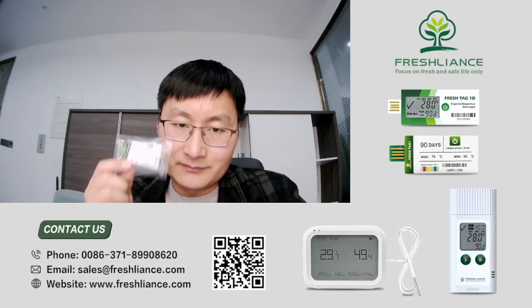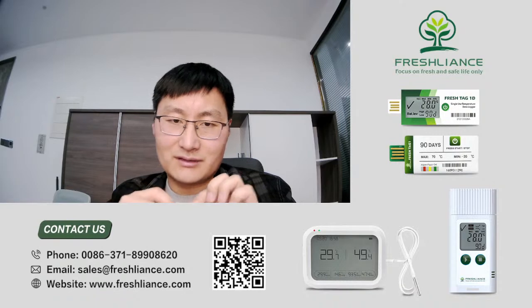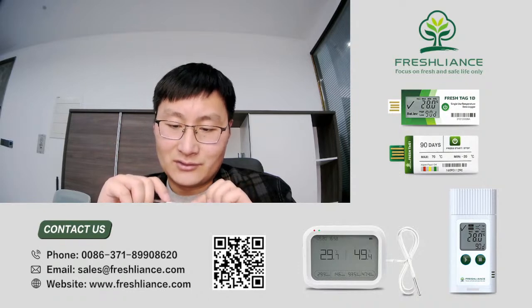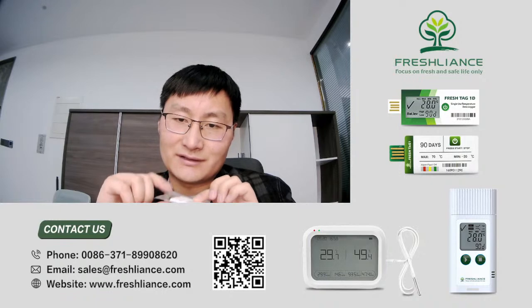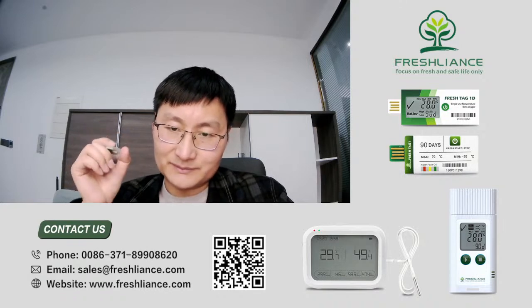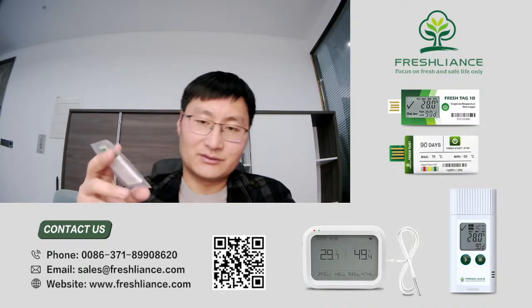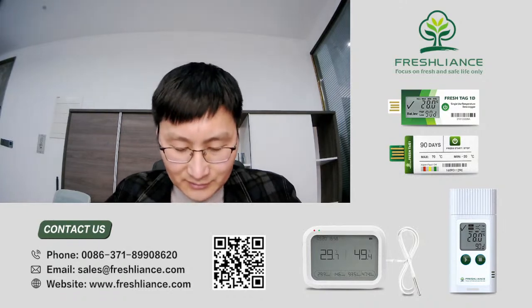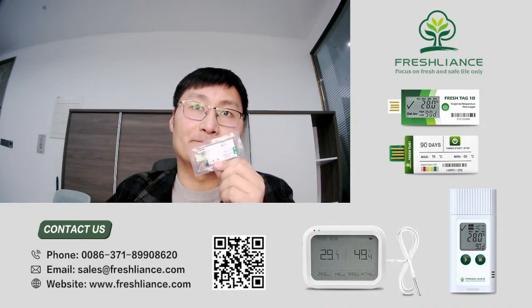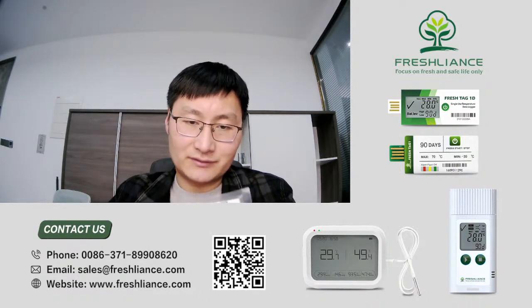every 30 seconds. So when you want to stop the logger, you can press the button and hold it for 3 seconds. The red indicator will flash 3 times, and then it will be stopped. After stopping, you can plug it into the computer. If you didn't stop it, you can also plug it into the computer to get the report. The yellow indicator is only for start delay. So if there is no start delay, the yellow indicator will not flash.